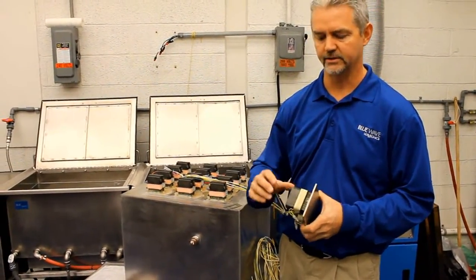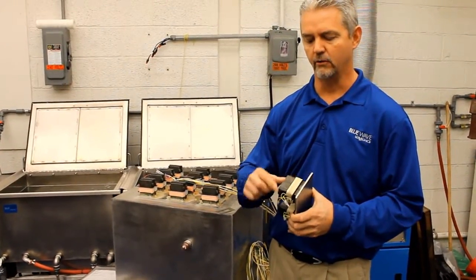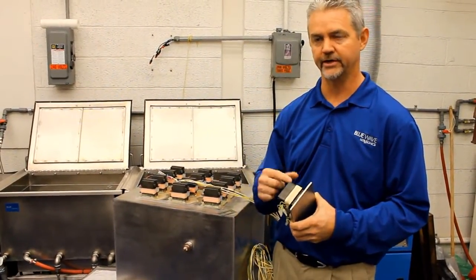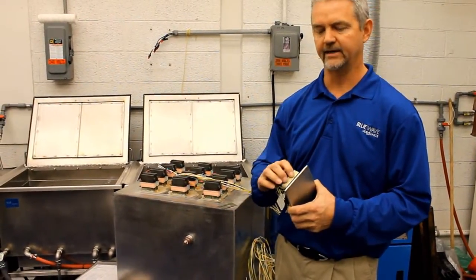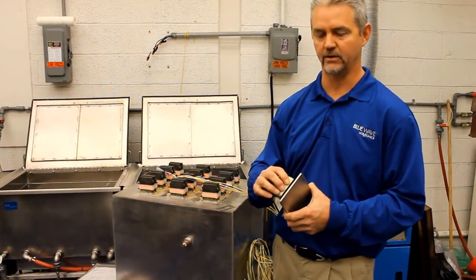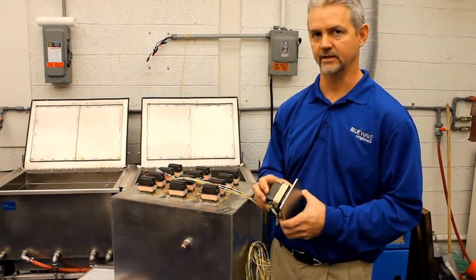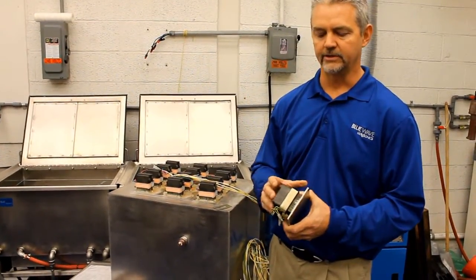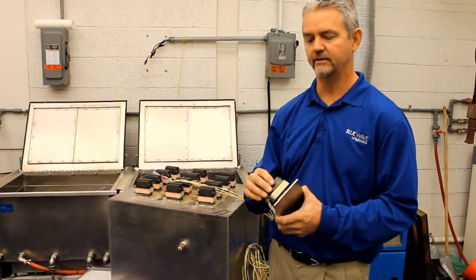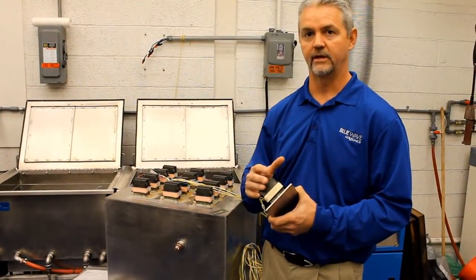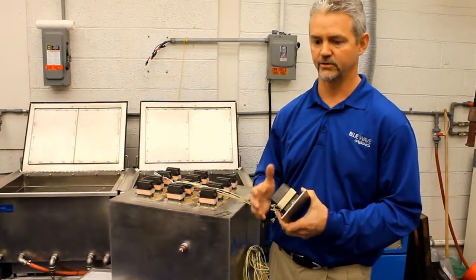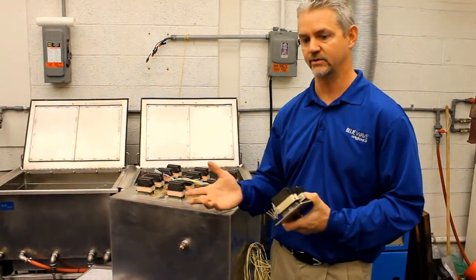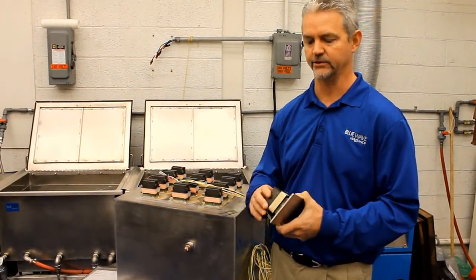What Blue Wave does is we put a coil around the stack and generate a 30 kHz frequency through that coil. Every time a magnetic field is set up in that coil, the nickel sees it and contracts. It's a very heavy-duty design, and because it's inherent in material, the magnetostrictive properties will never degrade. You get the same performance today as you get 20 years, 30 years, 50 years down the road.